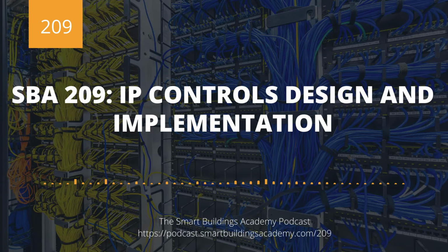via static IP addressing, or they can be dynamically assigned from a dynamic host configuration protocol (DHCP) pool. So a subnet will consist of a set of IP addresses that then can be assigned to the field controllers, and those field controllers' IP addresses are matched to their MAC addresses in the ARP table in the switch. Now that subnet can only communicate to devices within its subnet.